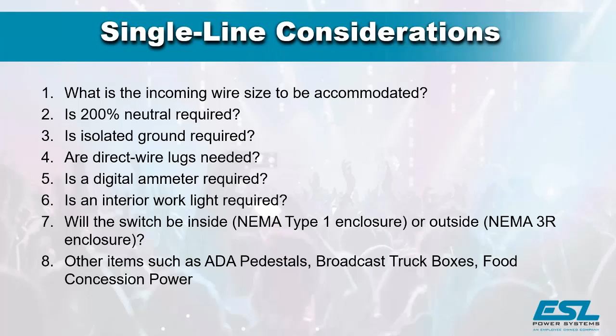Just a quick look at how you may see these. Sometimes I see them drawn as disconnects, like on the left -- the engineer is drawing it as a disconnect, but it's actually a company switch, as you can tell from the wording calling it a company switch. On the right, the engineer got really fancy and drew a pictogram of a company switch, even including double neutral at the bottom, as you can see. Very detailed, and on both examples they were good about calling out the conduit and the incoming wires. So that's wonderful.